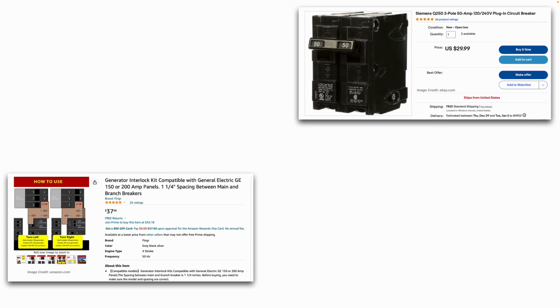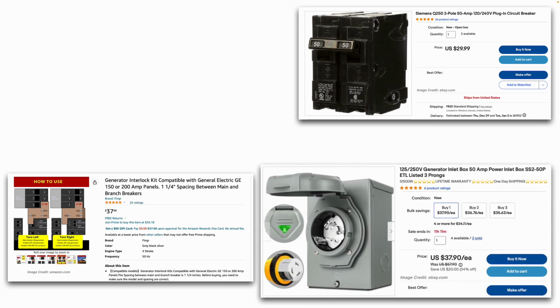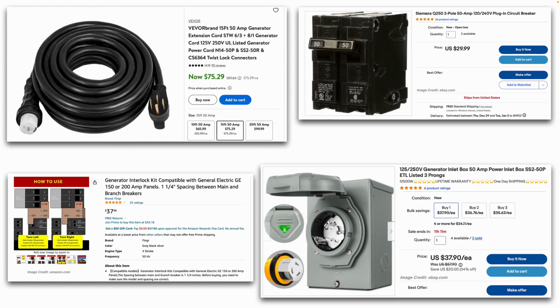And keep in mind, even if you do one of these interlock kits, this one costs, what, $38? You're also going to need to have a 2-pole 50 amp breaker installed in your panel. You're also going to need to buy the power inlet box that you would mount to the outside wall of your house. This one's $37. And then you're also going to need to buy the power cord that connects your generator to the inlet box on the side of your house. These come in different lengths, or if you're handy, you can buy the cord by itself with no ends on it, and then you can buy the plug separately and make it yourself. Personally, I think it's easier, and the cost is negligible as far as the difference between making it yourself or just buying one that's already pre-made.